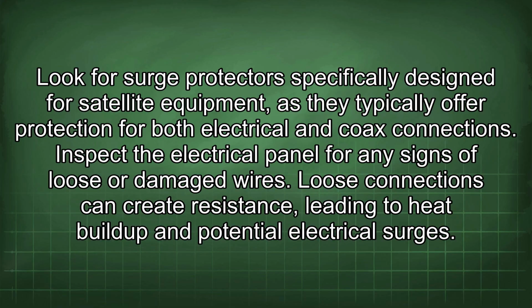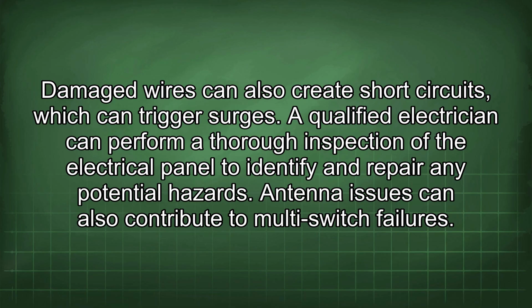Inspect the electrical panel for any signs of loose or damaged wires. Loose connections can create resistance, leading to heat buildup and potential electrical surges. Damaged wires can also create short circuits, which can trigger surges. A qualified electrician can perform a thorough inspection of the electrical panel to identify and repair any potential hazards.